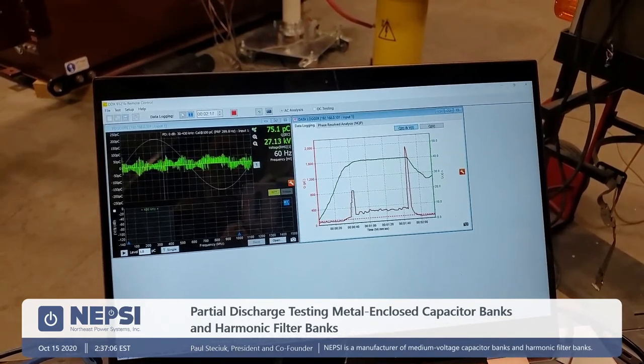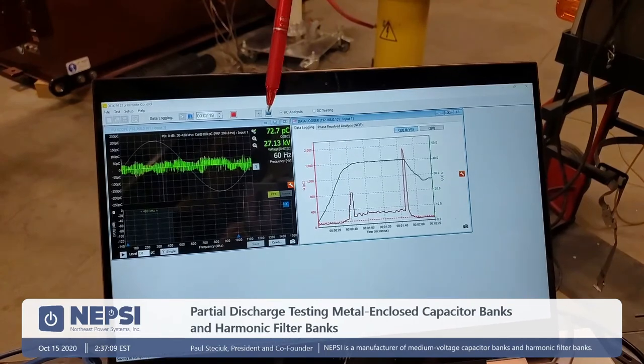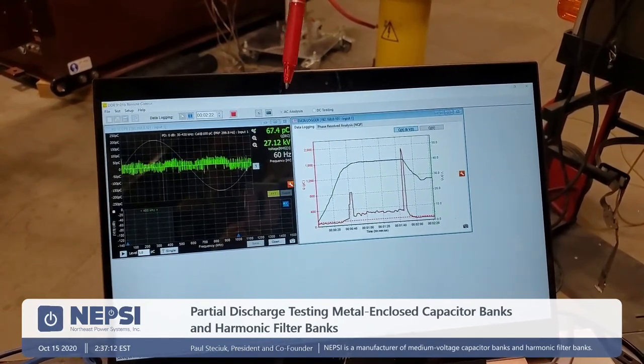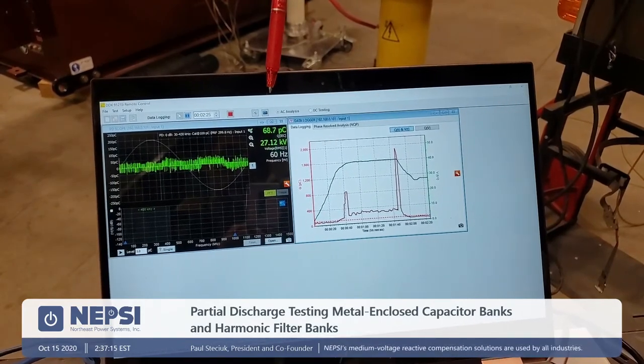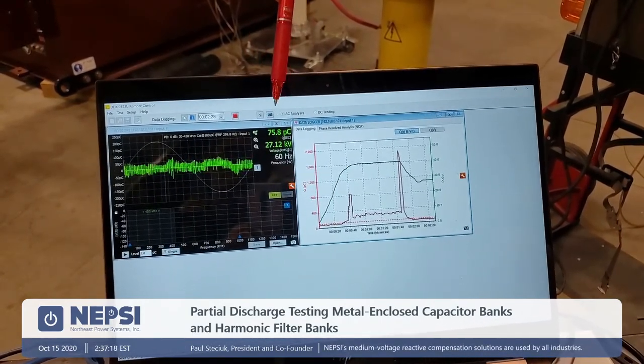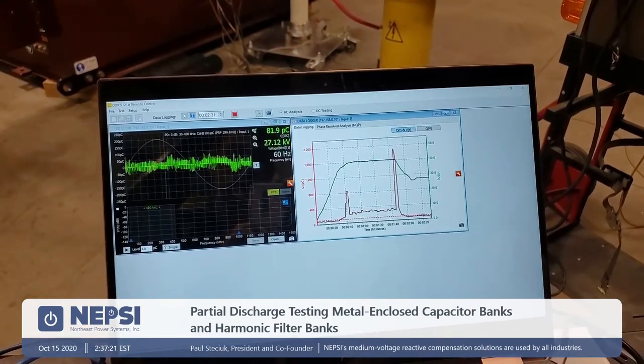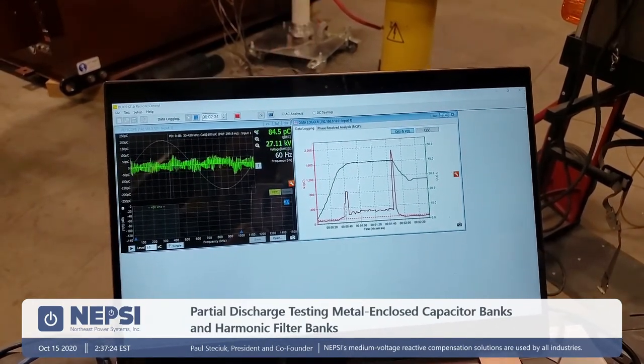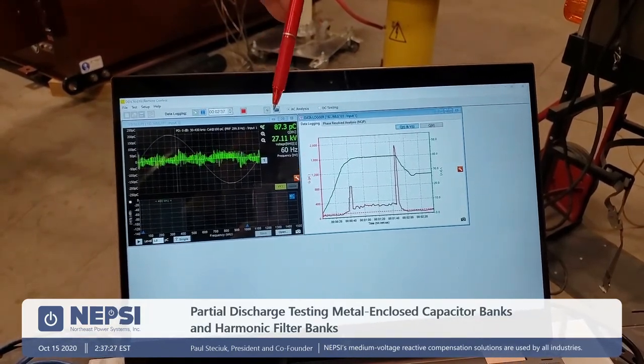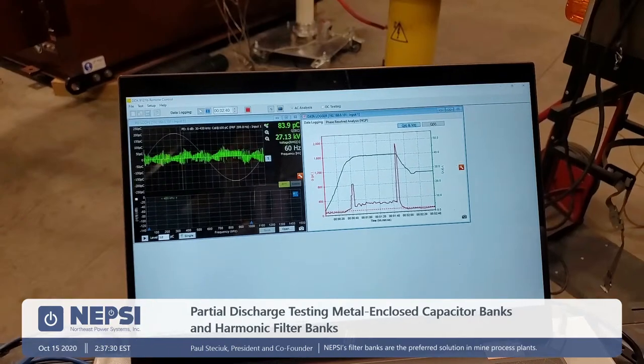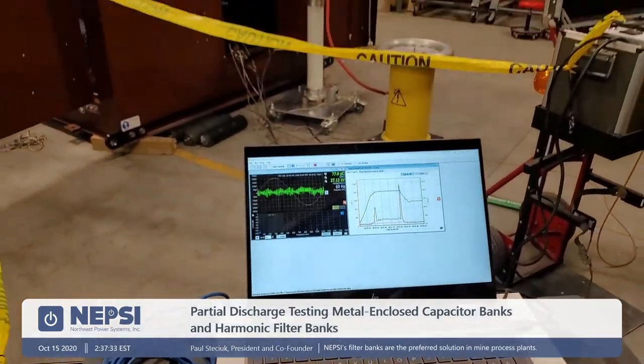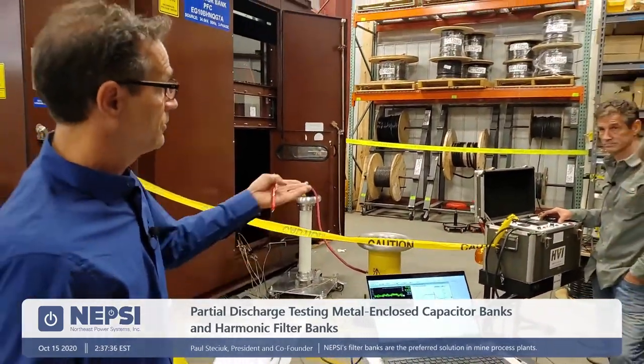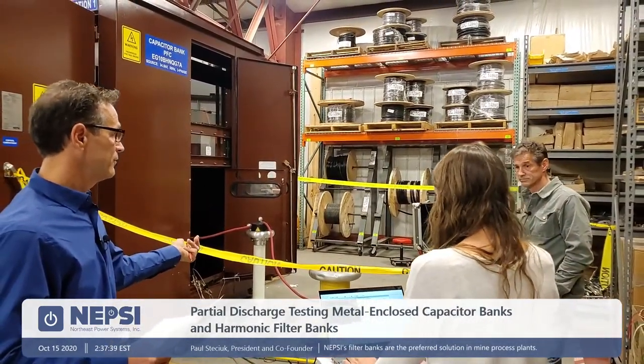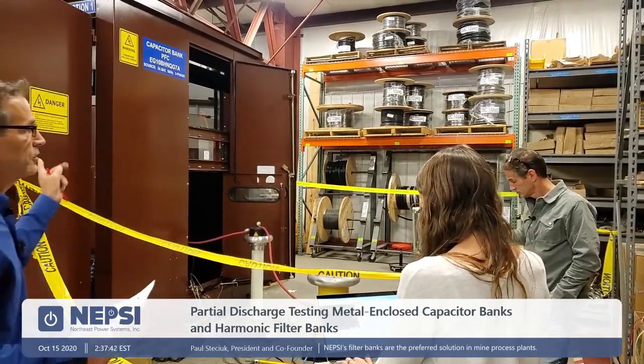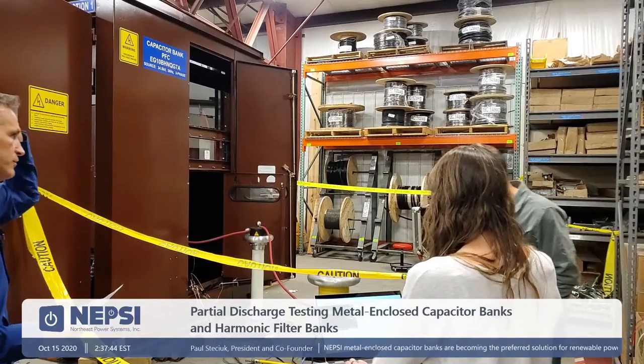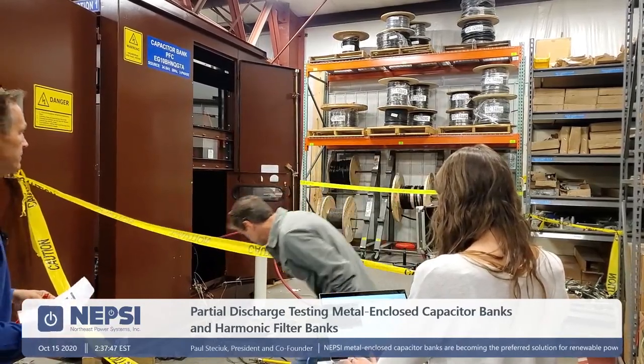We're at 27.13 kV here. And you can see that the picocoulombs is below 100. The test standards dictate that you'd be below 100 at what is called the extinction voltage. So here, we are below that extinction voltage. The 27.11 kV is what's required by the standard, and again, we're below 100. So this would be considered a pass on this test. So normally what would be done is you would turn the equipment off and ground it. Why don't you do that real quick, and we'll just talk about a couple of things you might have found in the process of doing this over the last year or so.